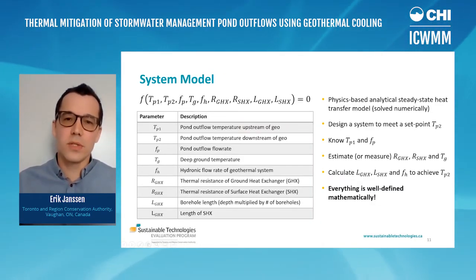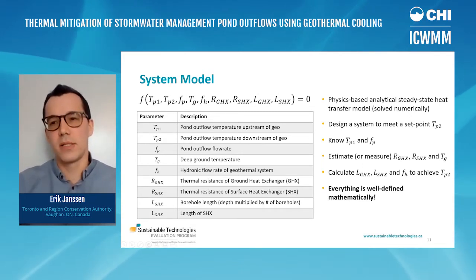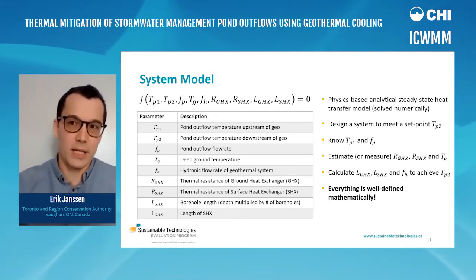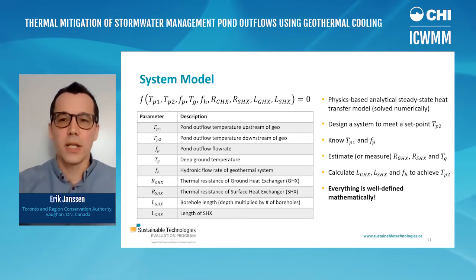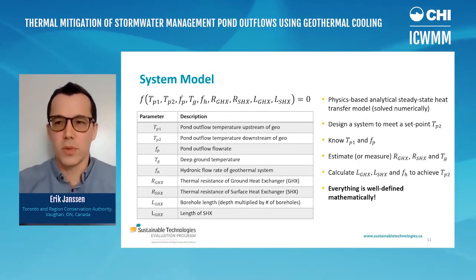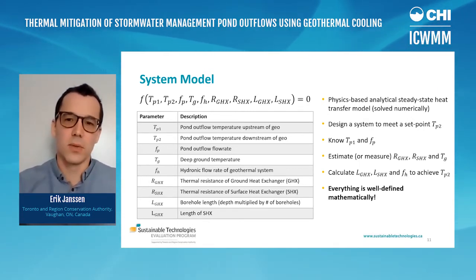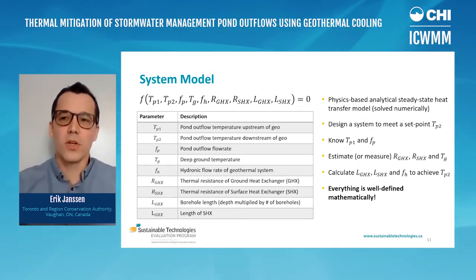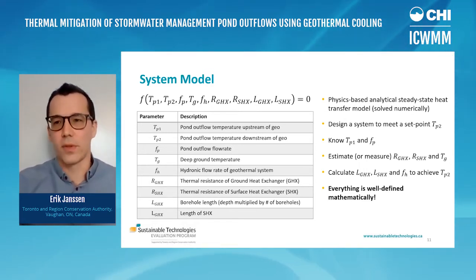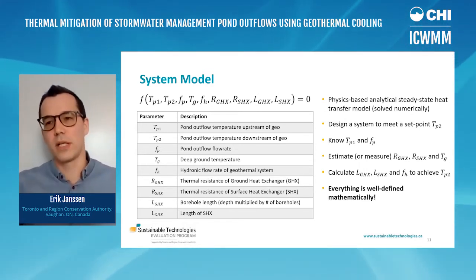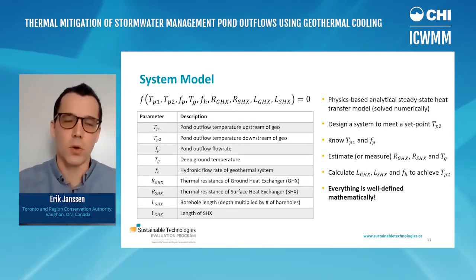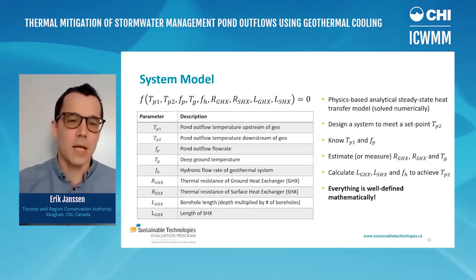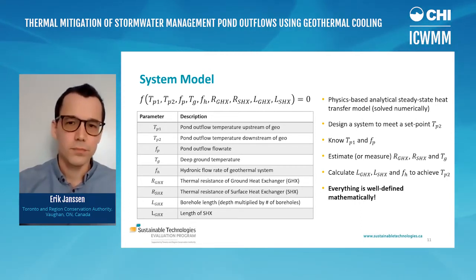Now, the good news is that because these systems are from an established sector already in heating and cooling buildings, the math is already quite well defined. So it's a physics-based analytical steady state heat transfer model that in our case we would solve numerically, but that's quite easy to do. What we had to do in our research was essentially take the math for the ground heat exchanger and the surface water heat exchanger and just put it together to create an overall system model. This table shows all the parameters that are important that govern the system performance.